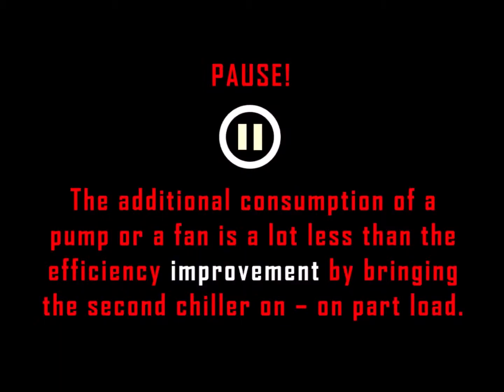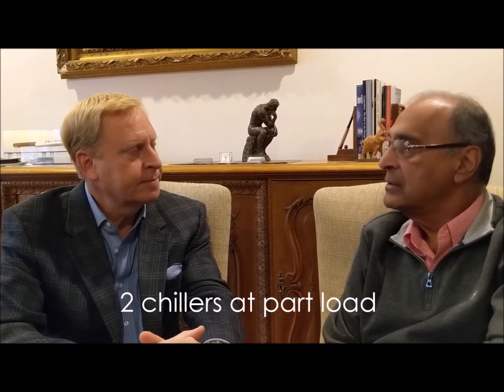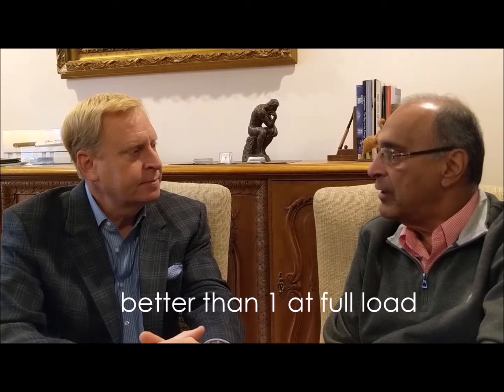But what they fail to realize is that the additional consumption of a pump or a fan is a lot less than the efficiency improvement by bringing the second chiller on part load. And by running 2 chillers at part load, you're better off than running 1 chiller full load and the other one at 0.